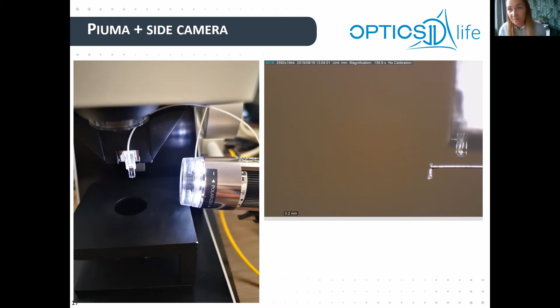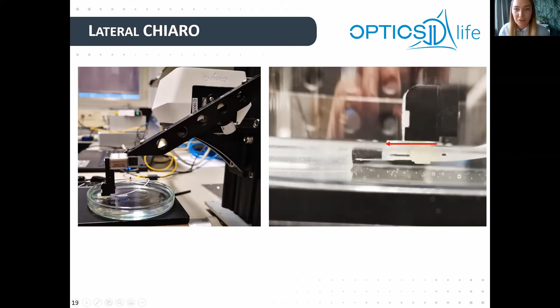Also, if your application has changed to where you need higher imaging resolution, you can get a Chiaro head, which can be connected to the same controller and interferometer as Piuma. So you can expand your applications. In addition, something new that we can perform now is lateral indentations with Chiaro. Here you can see that the piezo is actually facing the horizontal direction. And here the probe is indenting on the side of this glass Petri dish, for calibration, for example. And here we have a piece of Petrisoft and we're just indenting on the side. You can also imagine that this can be done on single cells. So if you are interested, you could also get this kind of configuration for some interesting experiment.